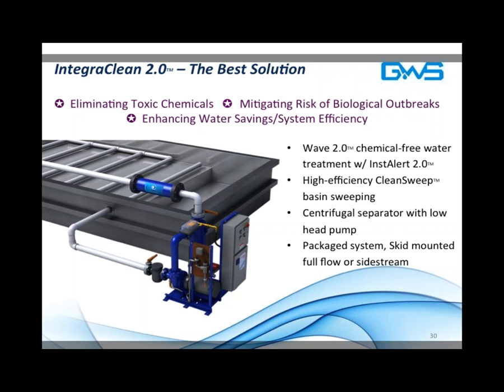In our case, the system is so effective at biological control that when we do heterotrophic independent lab certified tests, they often come back far lower than the CTI recommended standard of 10,000 colony forming units, in numbers closer to say 500 or possibly 1,000, somewhere in that range. That corresponds to absolutely no sensation of biofilm in a cooling tower. So we know that if we have circulation within the cooling tower and the wave is on and its set parameters are appropriate, then we know we're controlling biofilm to that degree. So no specific tests are required.